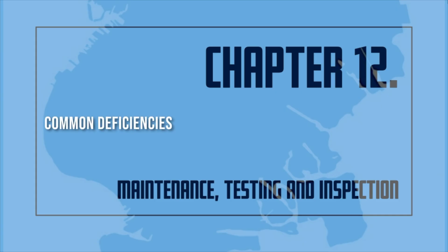Common deficiencies. The most common sprinkler system deficiencies include painted or loaded sprinkler heads, building contents located less than 18 inches below sprinkler deflectors, changes from the original wall locations, ceiling heights, and positioning of mechanical equipment. For concealed sprinkler systems, cover plates with non-factory coatings, the lack of required gap between cover plate and ceiling, and blocking of the spray patterns from light fixtures too close to the sprinklers are the most common deficiencies seen in the field. Missing trim or cover plates not attached properly to sprinklers may indicate hanger deficiencies and may not allow the sprinkler deflectors to drop below the ceiling, blocking the spray pattern.